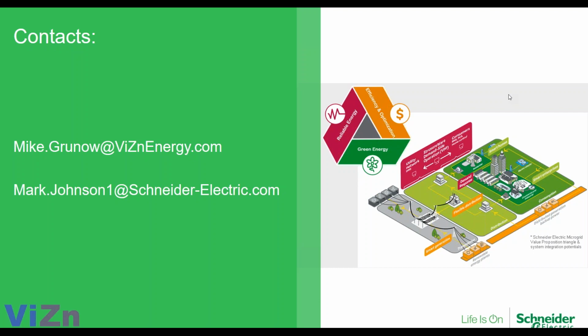Now, come January, February of 2017, the nice thing about flow batteries is if you want to go from kilowatt hour rating X to rating 2X, all you need to do is take the energy module, the tanks you saw, and double their size. You can use the same nominal stack design, same power generator, same engine, and just pump more fluid through it. So next year we're moving to a 4-hour battery system, and we're actively quoting those systems now for delivery in mid-2017.